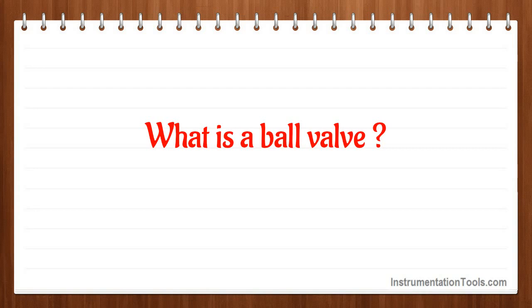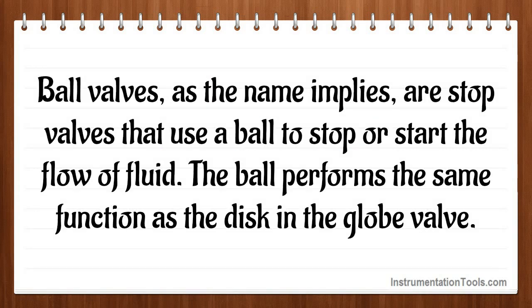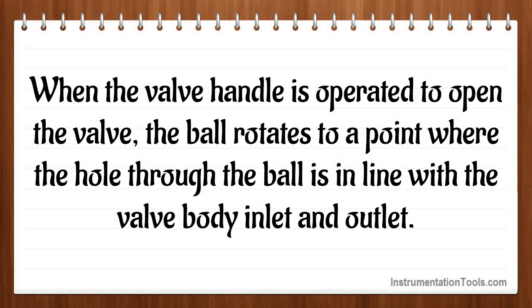What is a ball valve? Ball valves, as the name implies, are stop valves that use a ball to stop or start the flow of fluid. The ball performs the same function as the disc in the globe valve. When the valve handle is operated to open the valve, the ball rotates to a point where the hole through the ball is in line with the valve body inlet and outlet.